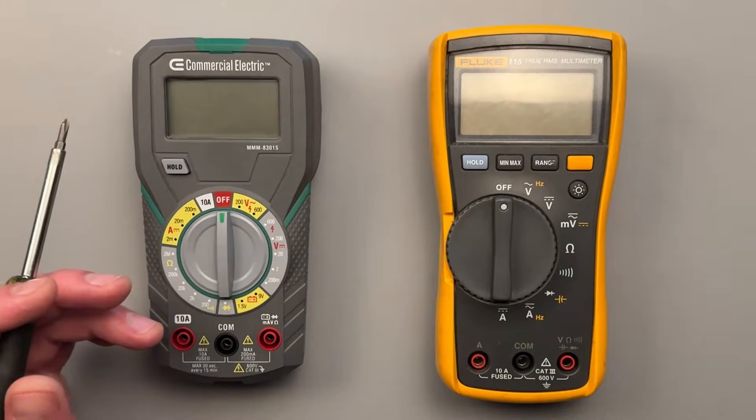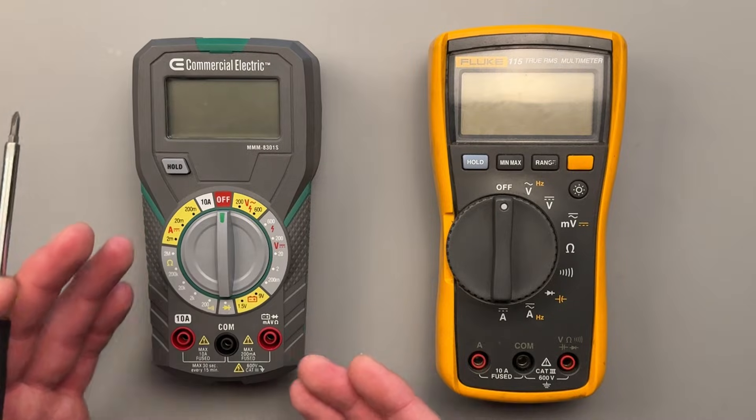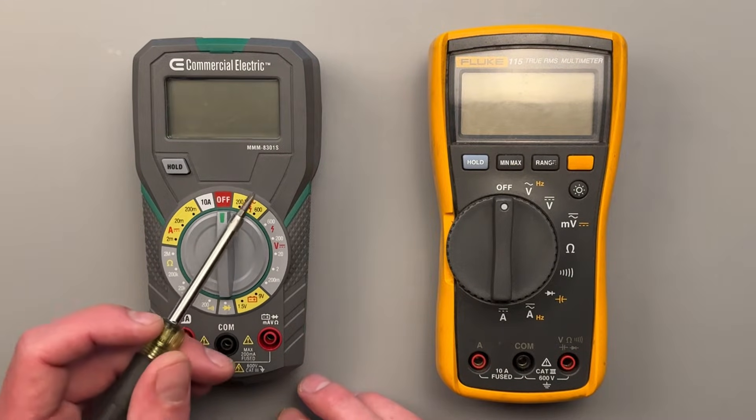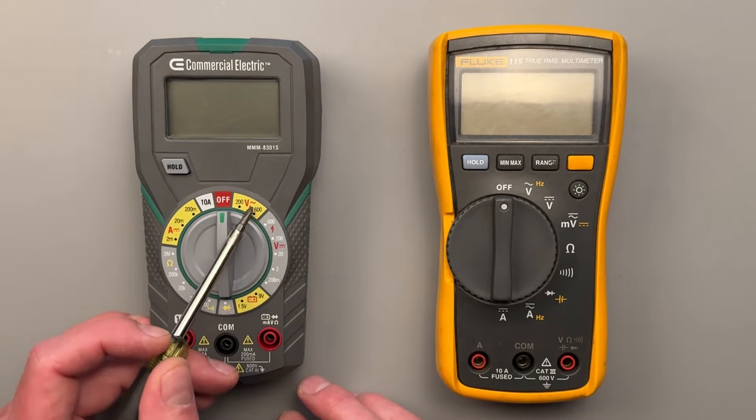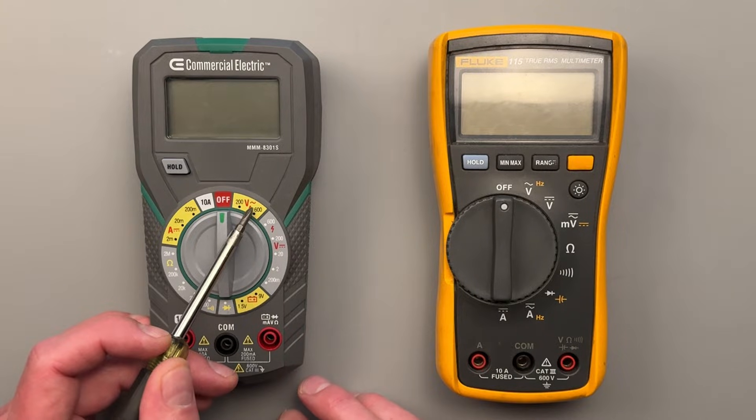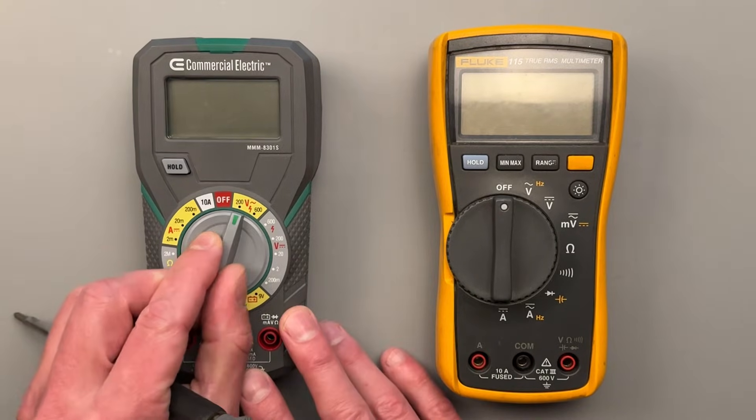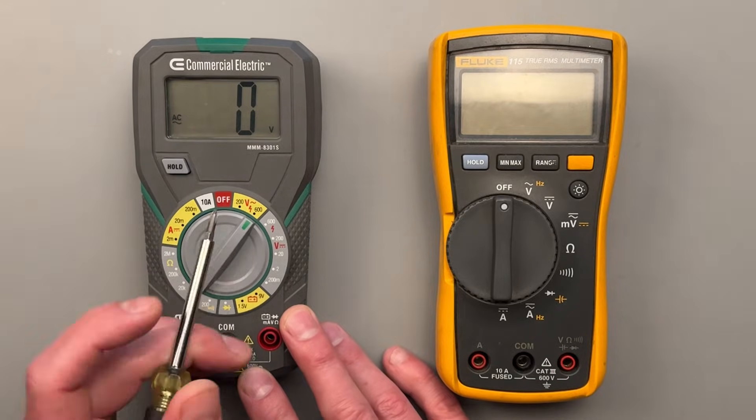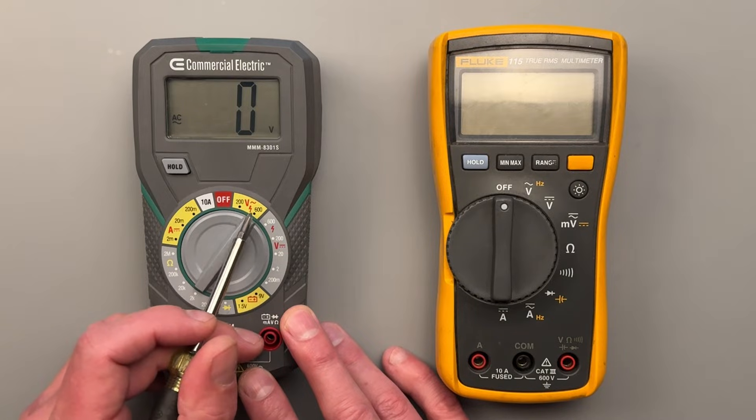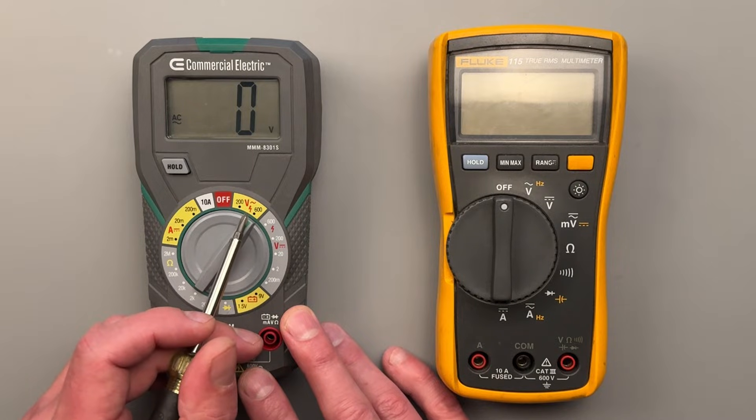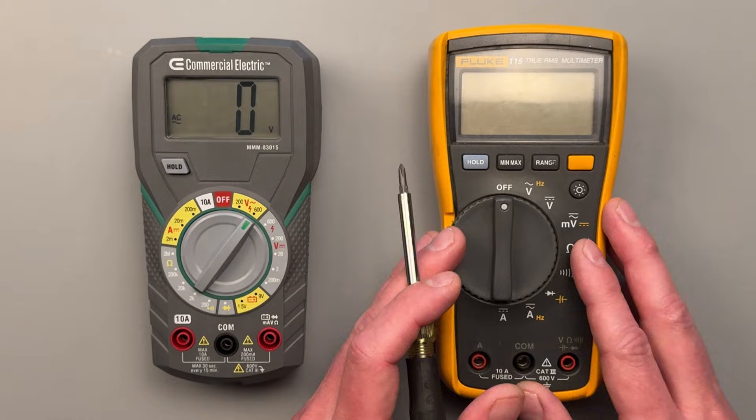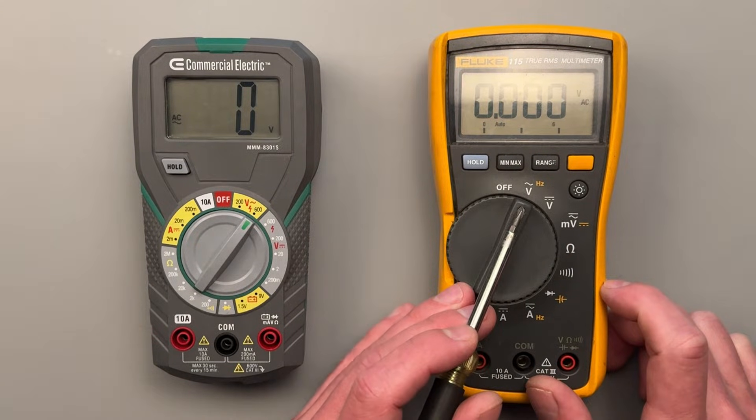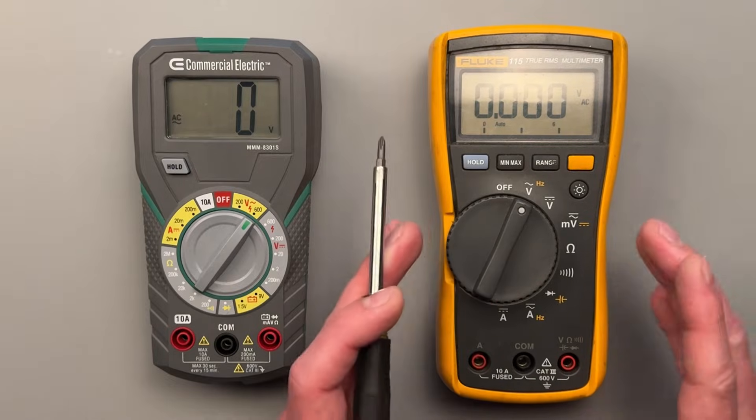Let's compare the settings of two meters. On the left is a manually selecting meter and on the right is an auto-ranging meter. For our voltage AC setting on the manual meter, we'll see that there are two options available. One option is indicating that it is able to read up to 200 volts AC. The second option is indicating that it is able to read up to 600 volts AC. The meter on the right simply has one AC voltage option and is capable of reading from 0 to 600 volts AC.